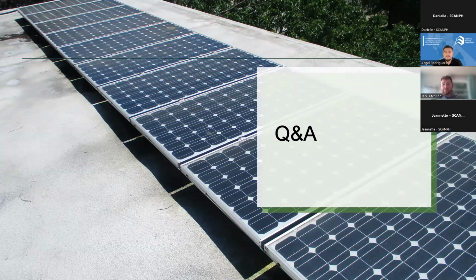However, can a heat pump water heater provide heating, even cooling, as well as domestic hot water? The answer to that is yes, and there are products available now. We typically don't recommend them yet because they're much less efficient than having two separate systems. That being said, there are products being developed that are going to be low GWP heat pump water heaters that can provide space heating and potentially cooling as well.